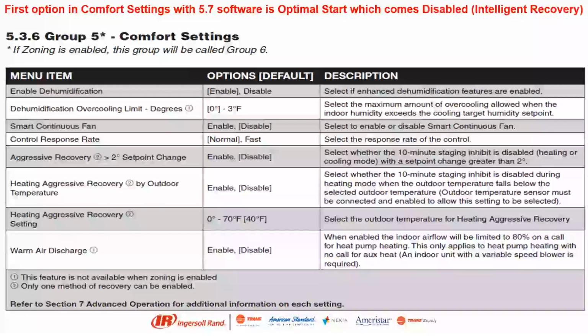So if you do have a homeowner that wants that quicker heat, if they're coming from 65 to 70 from nighttime setback, and we've got a 5-degree rise, it's going to take another 15 minutes, possibly, because if it does raise a degree or two, it's not going to energize the heat strip quite yet. So some homeowners want that quick heat. So we want to satisfy that room temperature as quick as possible. That way we can use the heat pump at a lower speed going forward. So that aggressive recovery does come into play quite a bit.